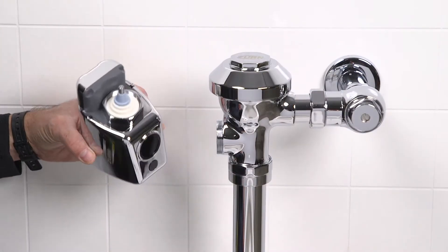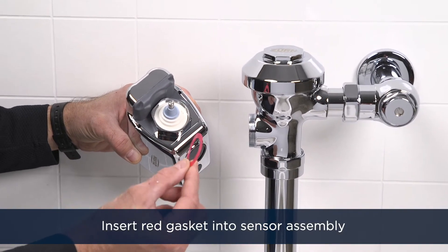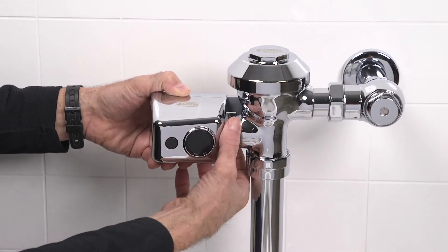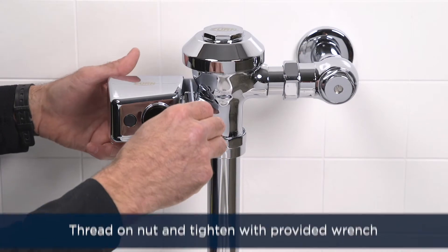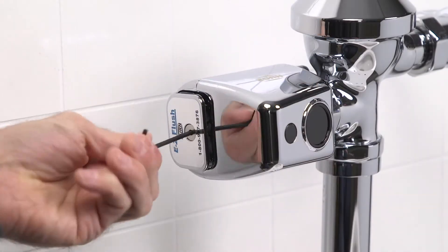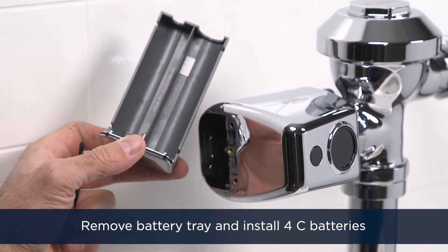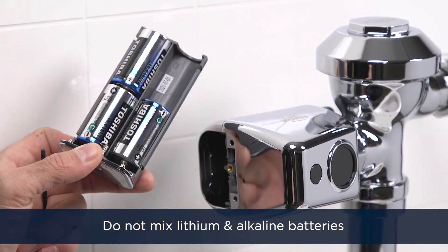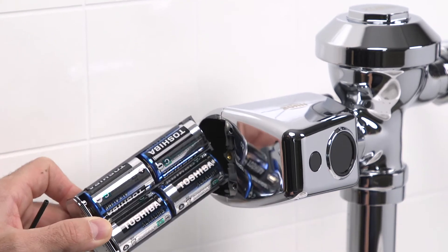Now we're ready to install the E-Flush sensor assembly. Insert the red gasket into the end of the sensor assembly and thread on the nut. Tighten the connection with the wrench supplied with your E-Flush sensor. Remove the battery tray from the sensor assembly with your allen wrench and install the four C batteries as depicted. Do not mix lithium and alkaline batteries — use one or the other. Reinstall the battery tray.